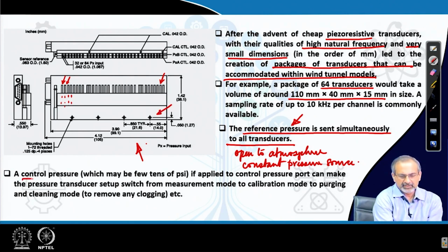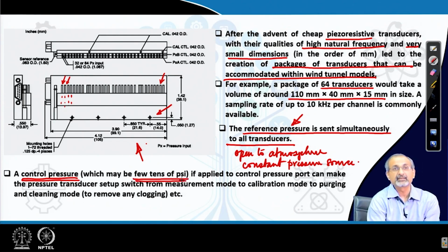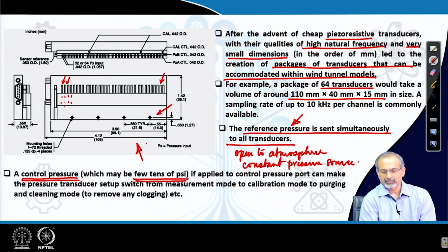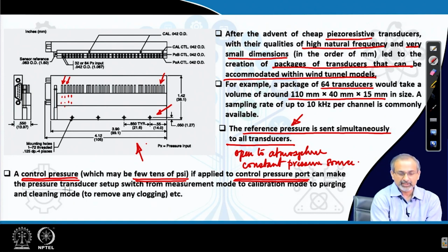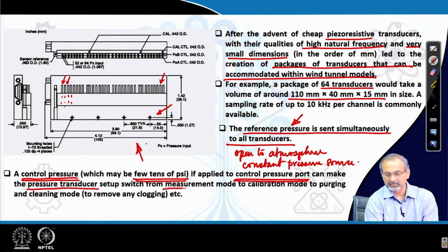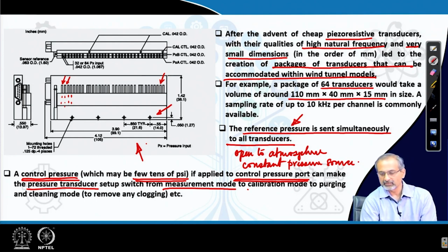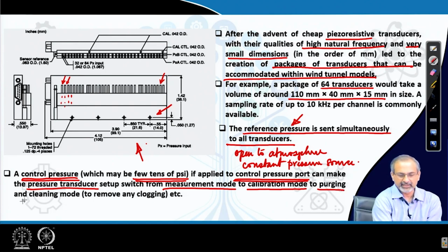Very often in these systems, a control pressure is additionally required, which may be in the order of a few tens of PSIs or a few ATMs. It has to be applied to a control pressure port, so that you can function the pressure transducer setup in different modes: a measurement mode where you are recording data from a model, or freshly calibrating the transducers, or purging and cleaning the transducers to remove clogging.